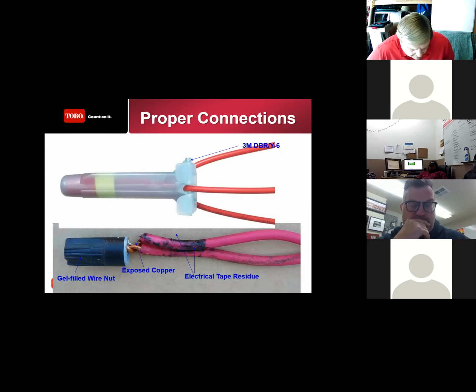But if you're not putting the wire insulation inside that connector, there's no waterproofing. There's no water protection. You've got exposed copper there. And oh, by the way, this guy pre-twisted the wire. If you look closely here, you can see right there where the copper is cracked because he pre-twisted, and then the wire nut's job is to twist it even more. That's going to cause a crack, and that's where my problem of corrosion is going to begin right there.